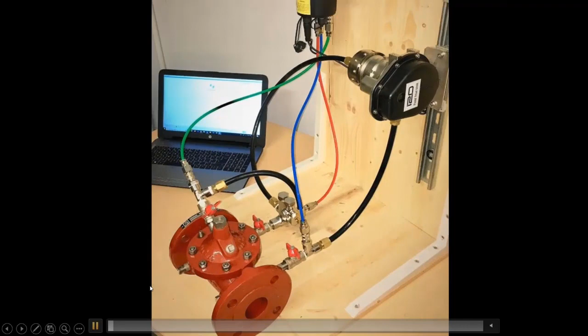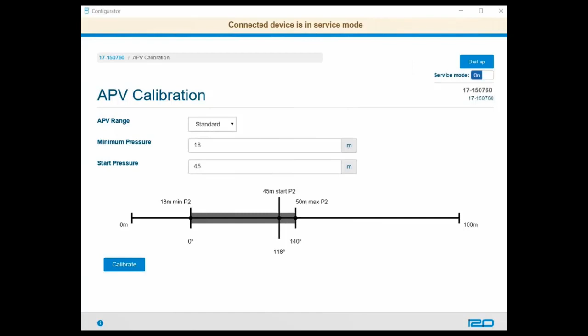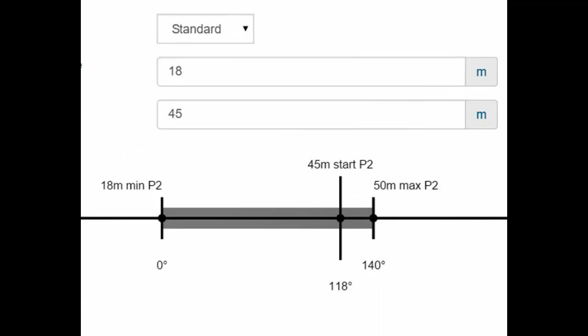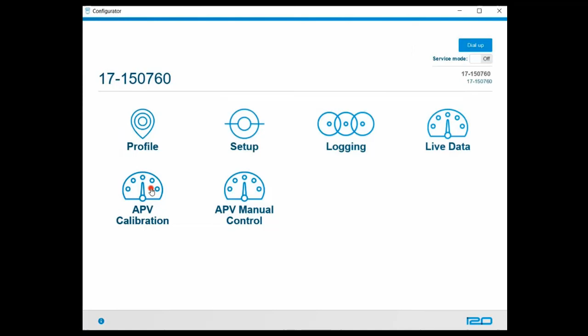So before opening the isolation valves that allow the APV to control your PRV, it's necessary to set the initial APV motor position to give the required downstream pressure. And that's what we mean by APV calibration. So when we connect a control logger, we need to select the main screen of the configurator and go to APV calibration. You need to be in service mode in order to proceed to calibrate the APV, so that's changed with a switch at the top.